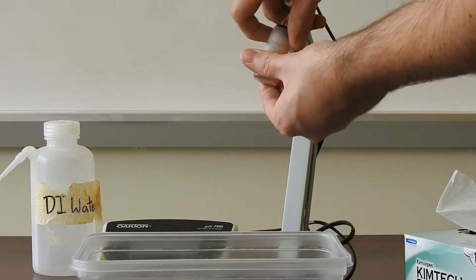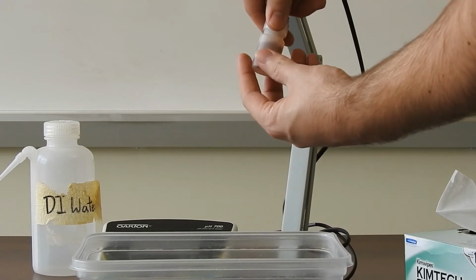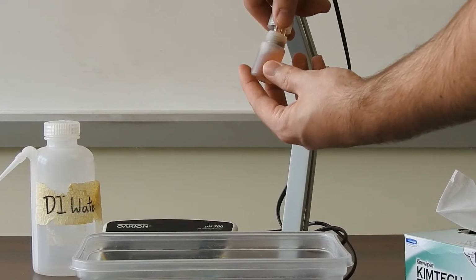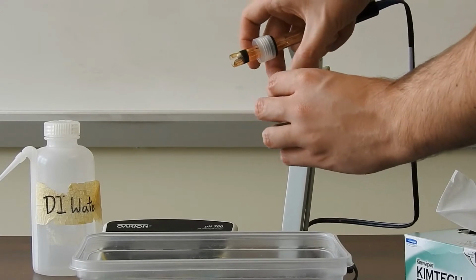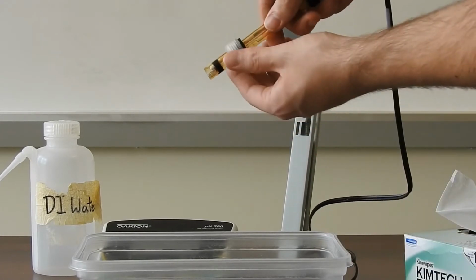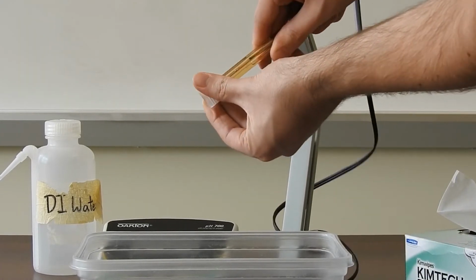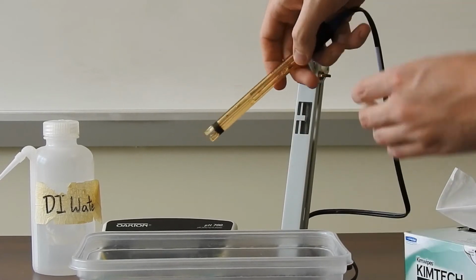One of the first things you'll want to do when you're ready to read pH is take the probe out of the storage solution. It's kept in that solution when the probe is not in use to keep the membrane at the end of the probe wet at all times, otherwise it can damage the instrument. So you'll just take that lower portion off, go ahead and unscrew it, and then slide that top part off.